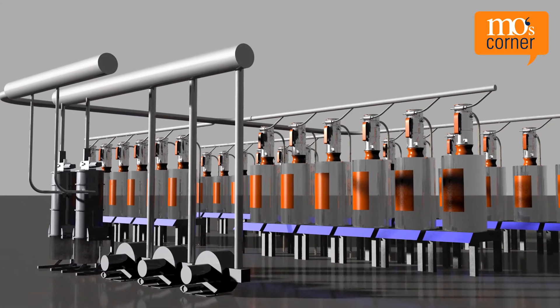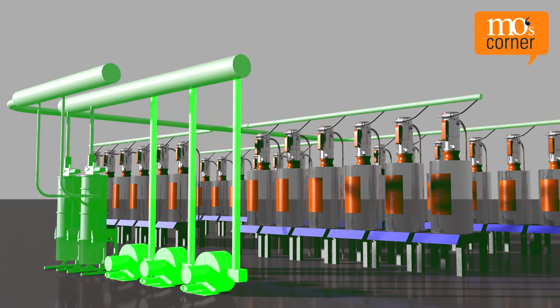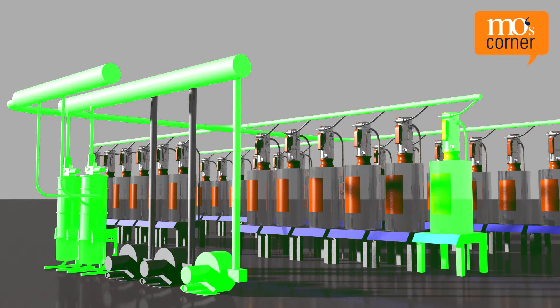This is how a central vacuum conveying system works. The vacuum pumps only run if the conveying system's internal pressure sinks below a specified value, for example 500 millibar. Conveyor 1 signals a material requisition. The conveying process can start immediately, because the vacuum required is already at hand. Shortly after, conveyor 2 signals a material requisition. This second conveying process also starts immediately, while the first process is still running.